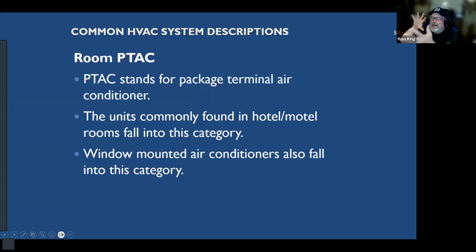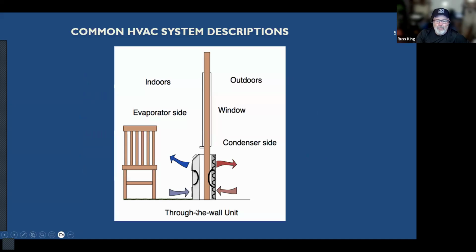A window air conditioner, just a little tiny window air conditioner that you set in your window, that's a package unit too. We call it a PTAC, package terminal air conditioner. Here's a PTAC that you would see in a hotel room. So the outside is the condenser, the inside is the evaporator coil side. The air is passing through and getting cold on this side, and the outside air is coming in and picking up heat. So the heat is being moved from the inside to the outside. We'll talk a little bit more about that.